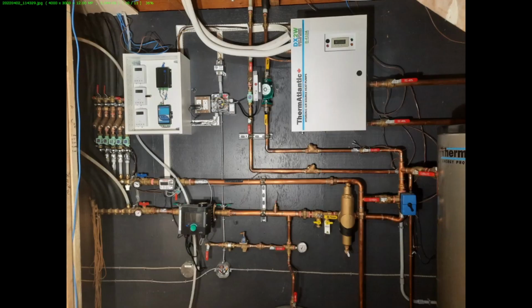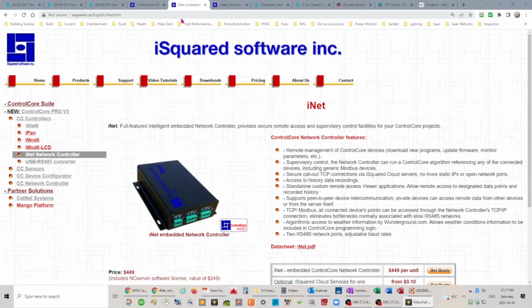Now let's go through some of the system components and how they operate in the system I've put together. At the very top of the system is the iNet server. It is the device that stores the program and allows for all communication between devices in the Modbus network. It also allows for the cloud storage of all parameter history and for remote management of the system. The controller has two COM ports. This would allow for two devices or two daisy chains of devices.